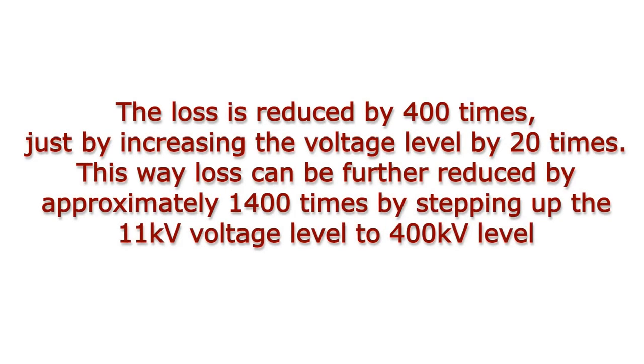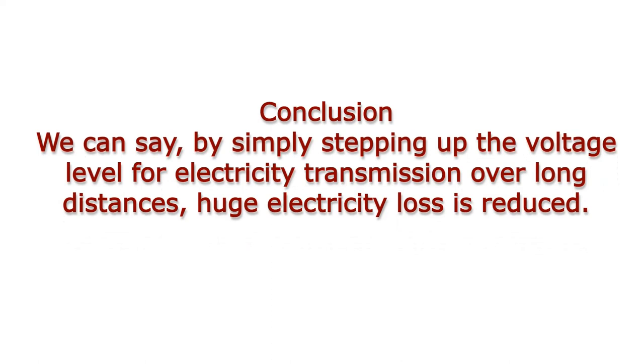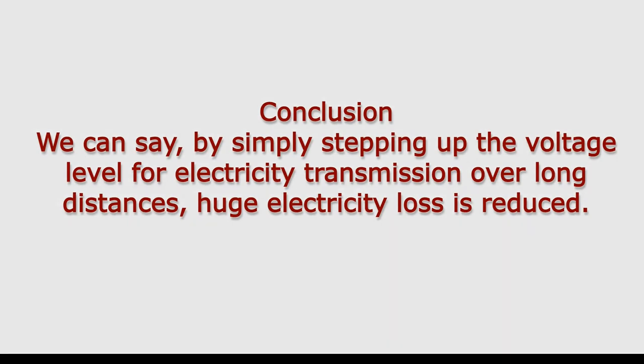After discussing both cases, we can see that the loss is reduced by 400 times just by increasing the voltage level by 20 times. This way, loss can be further reduced by approximately 1,400 times by stepping up the 11 kV voltage level to 400 kV. Simply put, as per Joule's equation of electrical heating, the loss is proportional to the square of the current, meaning the loss is inversely proportional to the square of the voltage. Hence, loss can be reduced proportionally to the square of the voltage step-up ratio. By simply stepping up the voltage level for electricity transmission over long distances, huge electricity loss is reduced.